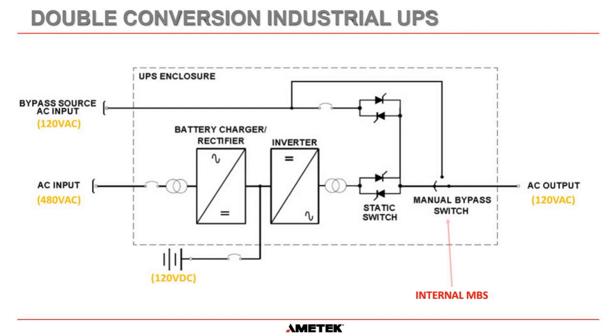Okay, so I'm back on the first drawing here. So the first slide, how do... okay, you're absolutely correct on this first slide here. This is a single line drawing and there isn't a breaker drawn here. How is the cable protected? There is going to be a fuse internal to the system, and that fuse should blow. So that should protect the cable, because there is no current protection on the RMBS. So if we're on inverter, actually in truth the fuse is there. If we're on inverter, that fuse would blow. If we're on bypass, this breaker here would trip. So we do have protection on the cable, either through this fuse here, or if we're in bypass, it would be on that breaker. Good questions though, I like that.